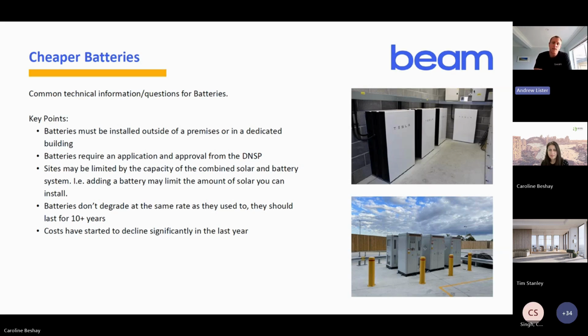So depending on whether you're a large or small site - if you're a large site with the VPP, you'd typically put the battery on what's called a child meter. That battery will still be constrained by the physical flow of electricity into and out of your site, but it's not going to override your site usage. It'll be capped at whatever your demand needs to be at the site, and will only charge with what's left over. But financially, that'll be on a separate meter, so the price you pay for using electricity under that child NMI will be based on the spot market, and same with discharging that battery.